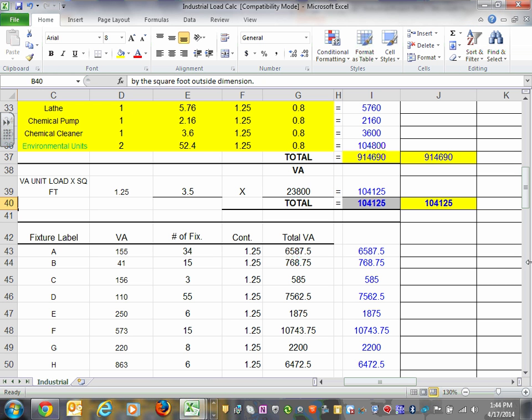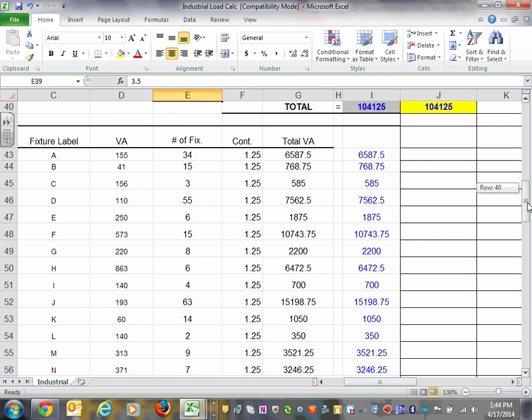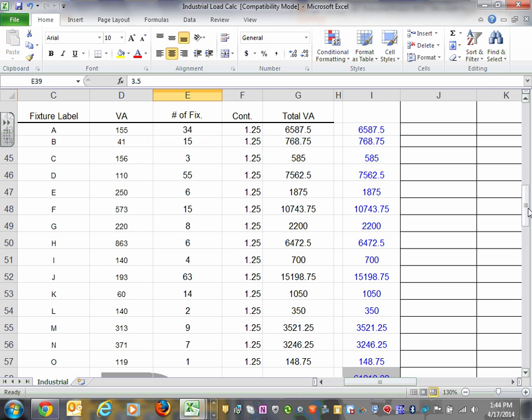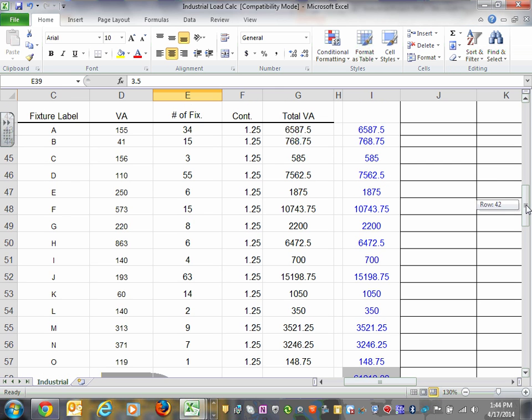Or you go to split hair. Take the support area, I can't remember, 3.5 volt amp and so on. Compare this value to the actual lighting fixture that you designed. You don't know that when we start. We have no idea what lighting fixture we use, right? So when you have your design, if you reach that point, you put all your fixtures based on the volt amp and the number of fixtures that you have, and their continuous loads, so you add them up, multiply by 1.25.